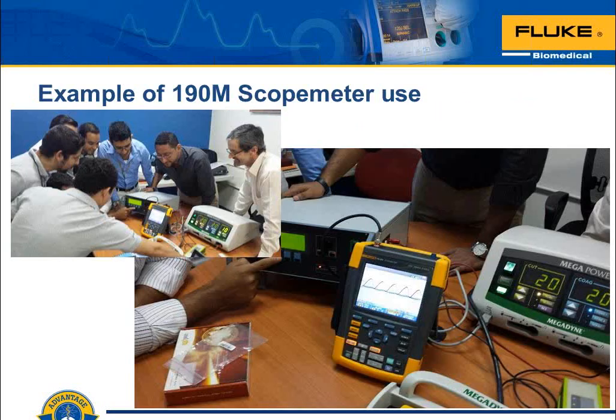Tip number 5, here's an example of hooking up the medical scope meter from Fluke Biomedical to look at those waveform outputs for the output energy. These guys came from Electrolab Medic in El Salvador, and I was just down with them 2 weeks ago. They were pretty adept at using the scope meter and dialing in the trigger so that they had just 1 or 2 waveforms on the screen, so you could really see the waveform and whether it was smooth delivery or whether there was some nuance, some problem in the waveform. So that's kind of how that would look. There's an output BNC connector on the front of the QAES, and that's where you hook up your test lead.